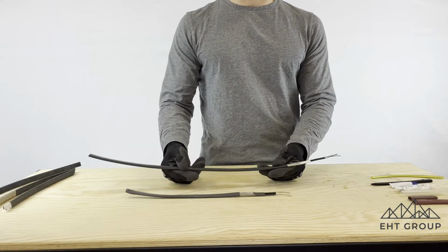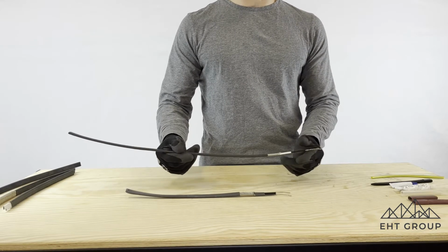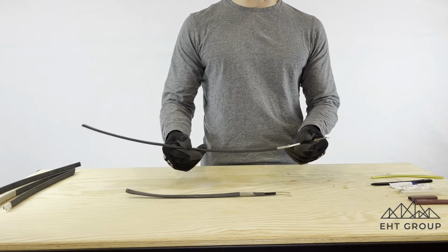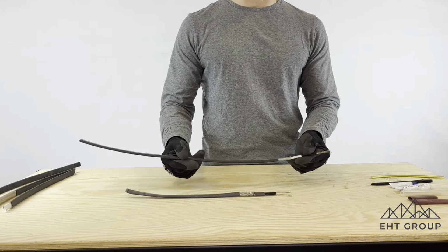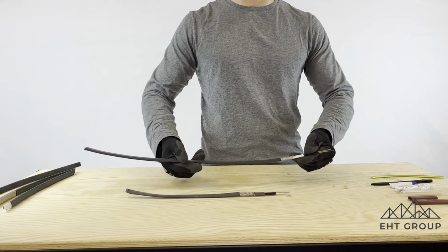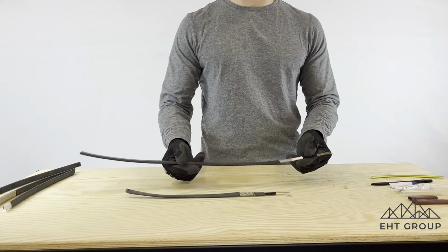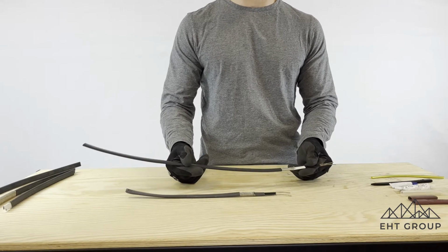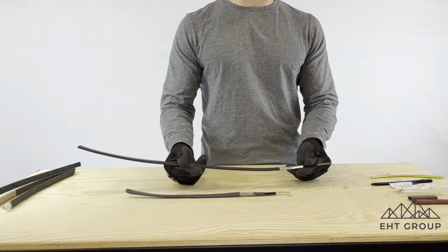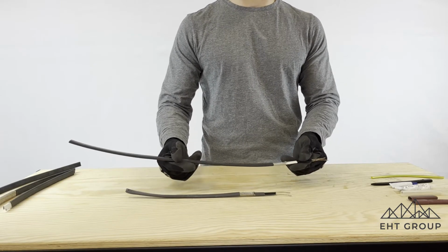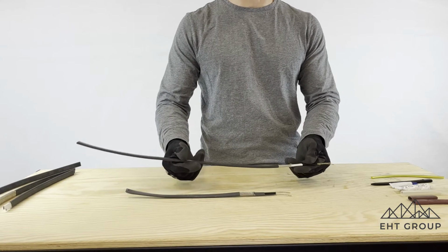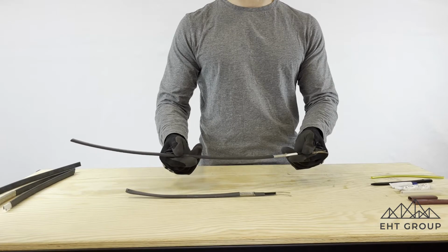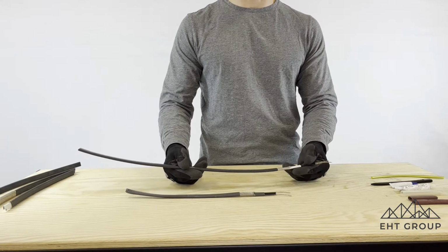The concern with SR cable is that it has inherently high inrush current properties, meaning that when SR cable gets installed, first of all, it should always be designed, meaning that the length of cable that should be used for your application should be known by whoever is installing it. Because oftentimes SR cable will just be installed and the electricians will just keep installing it until their application's done, and sometimes won't take into consideration that too much SR cable will end up causing high inrush current and unnecessary breaker trips.